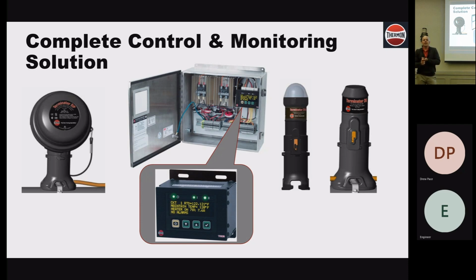If you are trying to maintain a temperature, will the control scheme help you to maintain that temperature? Absolutely, yes. That's different than on-off control, right? So those are actually two separate issues. You are going to have on-off control. The heat trace is either on or the heat trace is off. You're not typically going to have proportional control with trace just because the thermal system isn't that sensitive. So if you know PID control, you might have P, but you're not going to have the I and the D. So essentially it's on off.